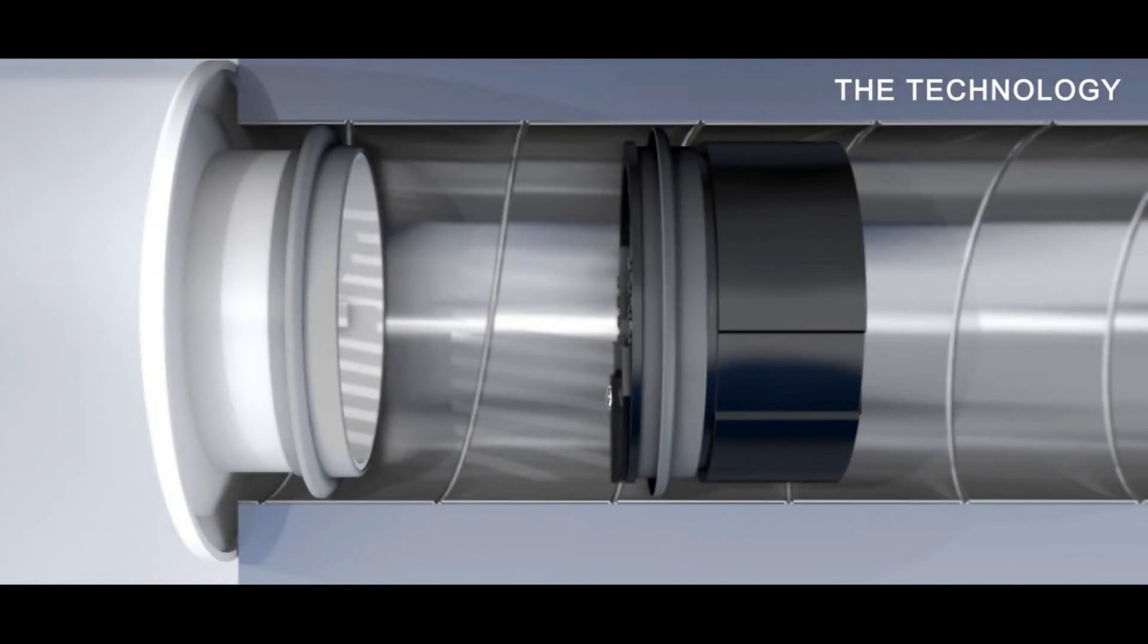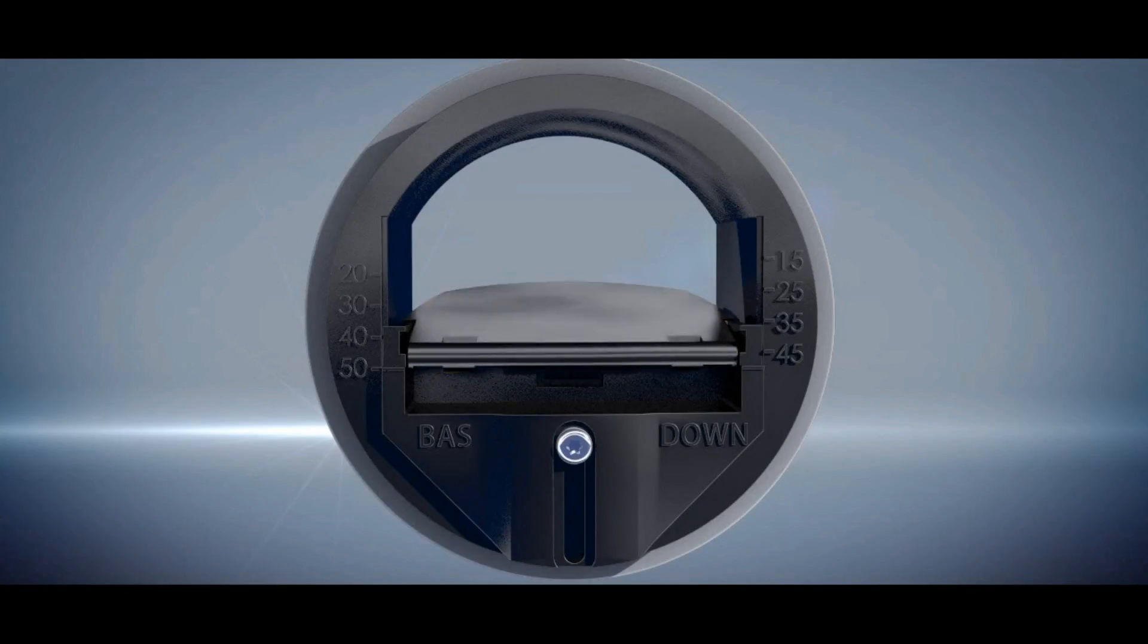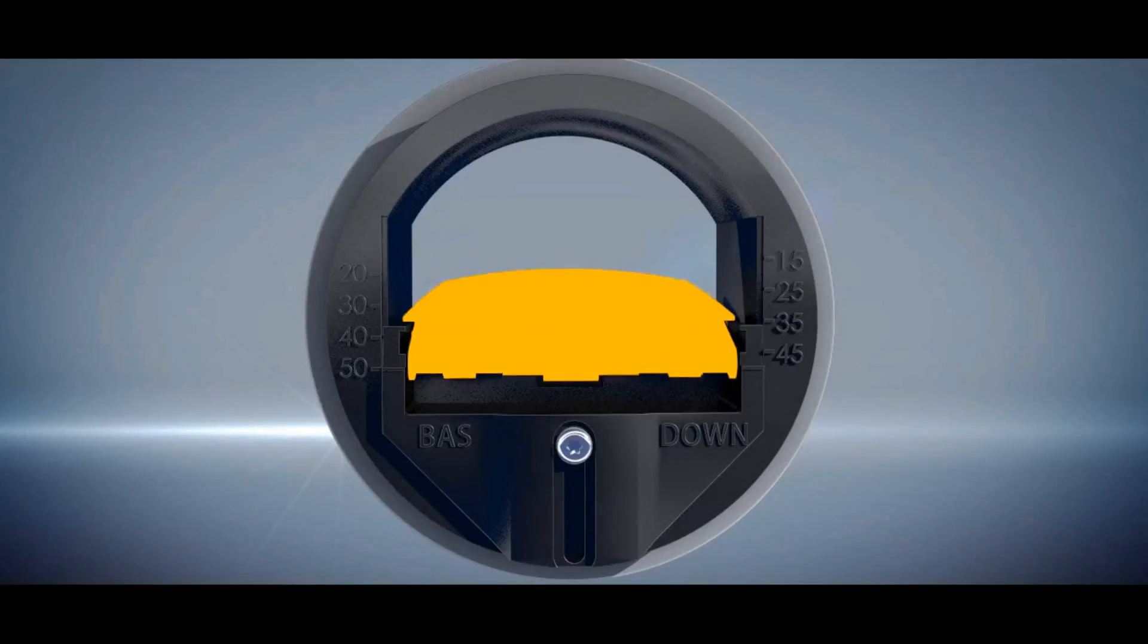The flap of the flow regulator will adjust according to the difference of pressure between the room and the duct. The flap opens or closes progressively to reduce or increase the amount of air needed to maintain a constant air flow in the duct.